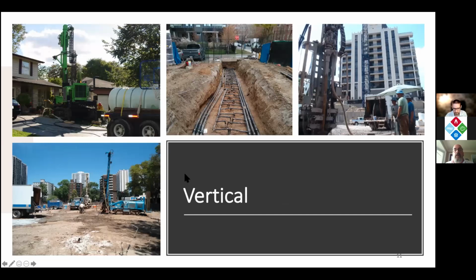Here we've got another one - this is a vertical loop system showing the vertical wells down the middle and then the supply and return lines on both sides. These are great because they take up a lot less room, so your land availability doesn't have to be as large as with a horizontal loop system where you need lots of acreage, but in a lot of situations that's not possible. So a vertical loop system is a great application, and as long as it's sized properly for the unit and the loads, it'll do equally as well.